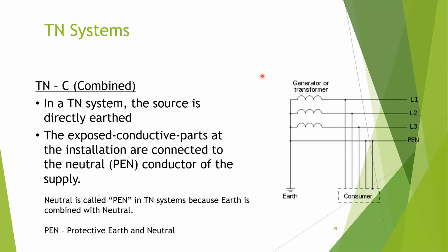Now we learned, I think we covered everything in the TT system. Now we are moving on to the TN system. So in the TN system, I said the source is directly connected to earth, and the installation is connected to neutral. This connection to neutral can be done in several ways. Depending on that way, we are categorizing these systems into a few other subcategories.